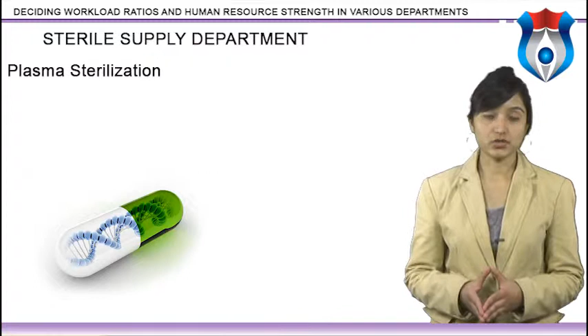Plasma sterilization. Plasma sterilization is used for thermolabile, reusable medical supplies made of plastic. The sterilization medium is low temperature plasma created in a high frequency electromagnetic field that interacts with vapors of 58% hydrogen peroxide in a high vacuum. Plasma sterilization is a dry sterilization process.